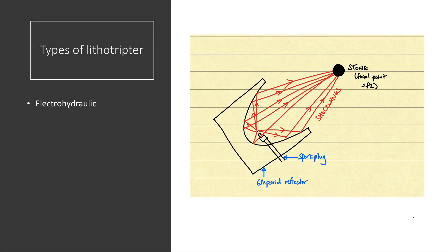Now let's look at the types of shockwave generator. The oldest type is the electrohydraulic lithotripsy, or EHL. This device has a spark source which generates a shockwave that is focused by an ellipsoidal reflector, as you can see in the picture. The key property of an ellipsoidal reflector is that it has two focal points: the F1 focal point, where the spark is generated, and the F2 focal point, which will be our stone.